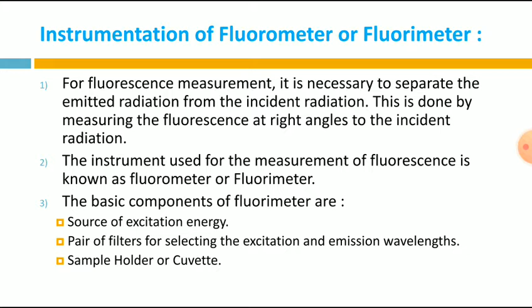Now we will first see a single beam fluorimeter, and its working. The light from a mercury vapor lamp, a source of UV light, is passed through a collimating lens and then through a primary filter. That means the first component is the source of light, the mercury vapor lamp, used as a source of radiation. That UV or visible light falls first on the collimating lens, and then on the primary filter. The filter transmits that part of the beam which can cause excitation of atoms to induce fluorescence.